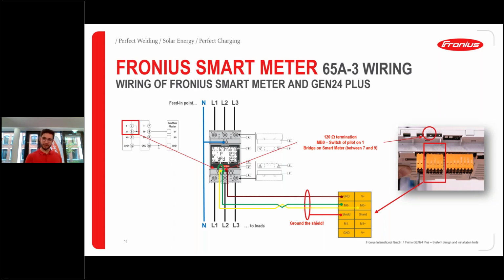And by that measurement, we then also know what's going on in the system. We can distribute the energy flow to charge and discharge the battery. And in case of a backup solution, we also know exactly that the grid is gone here. And after the smart meter, we have then a backup switch, and we can measure also out of our small grid, of our backup grid, if the grid has returned. So this is the reason why the Fronius smart meter is very important and necessary in a full backup scenario.